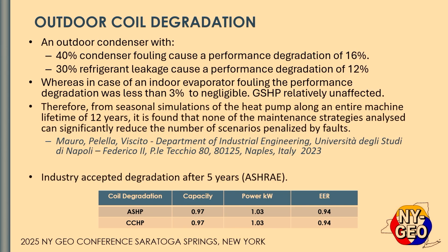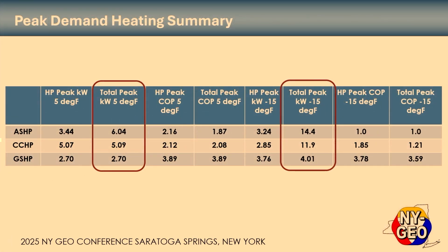with that 6%. So any number you see from a study, you need to look to see if it's installed units; it's probably got some sort of degradation in there. So here's the heating side, and heating's a little bit more complicated because I've included auxiliary heat and I've also done it at 2 different temperatures. So let's get set here with 5 degrees, okay? You can see the first 4 columns are all at 5 degree outdoor temperature. The last 4 columns are all at minus 15 degrees, okay?